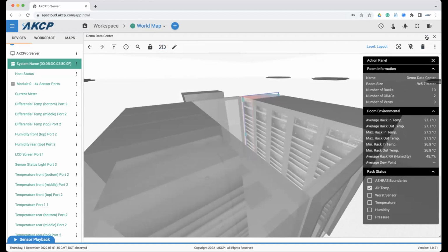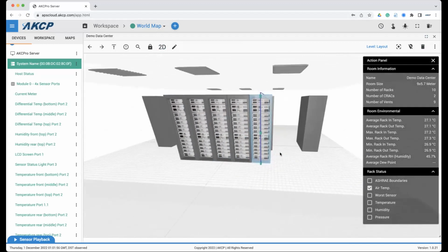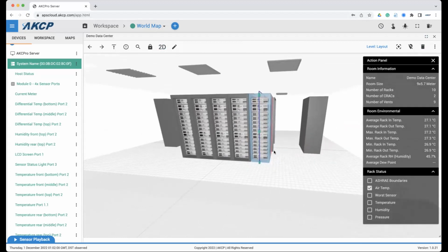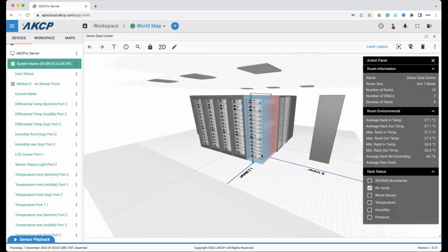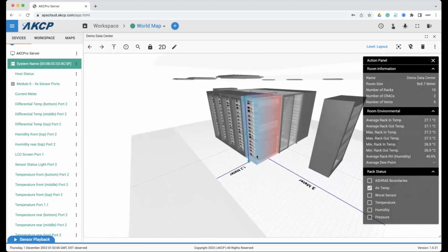Yeah. Well, I was just noticing that the thermal map sensors are drawn to be in the center of the rack. In practice, that's not how they're done usually, though, right? Usually the cable would be routed down the hinge side of the rack, so that obviously the door can still be closed.